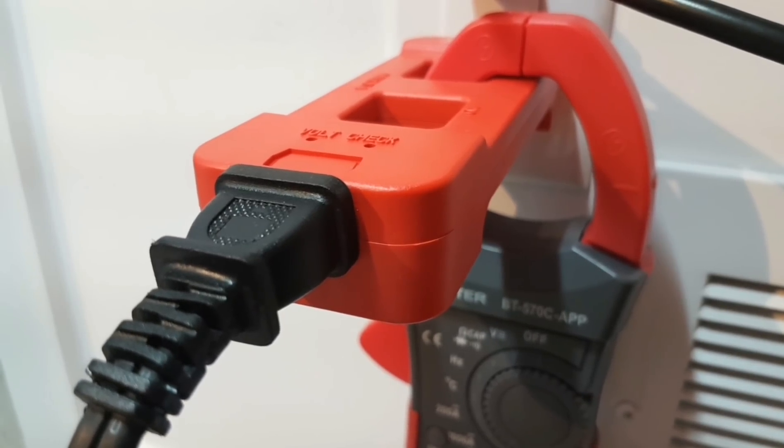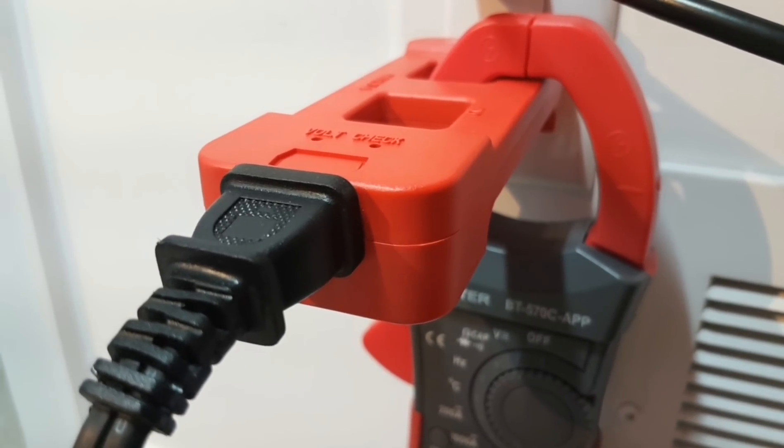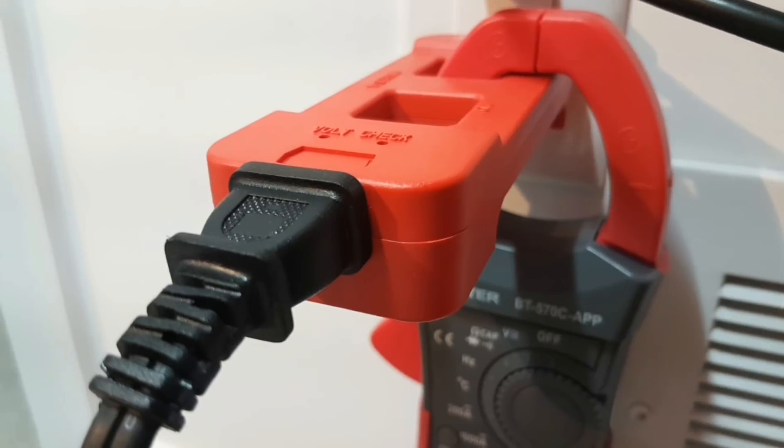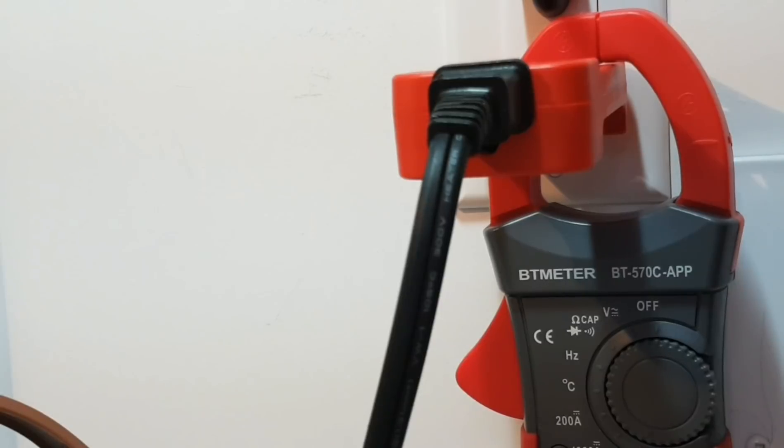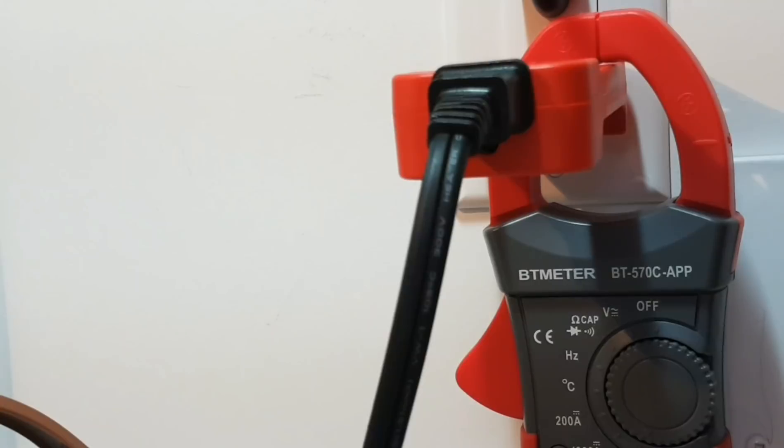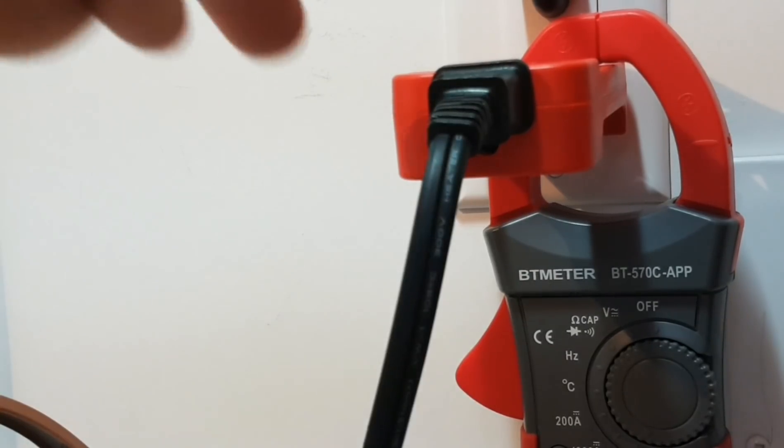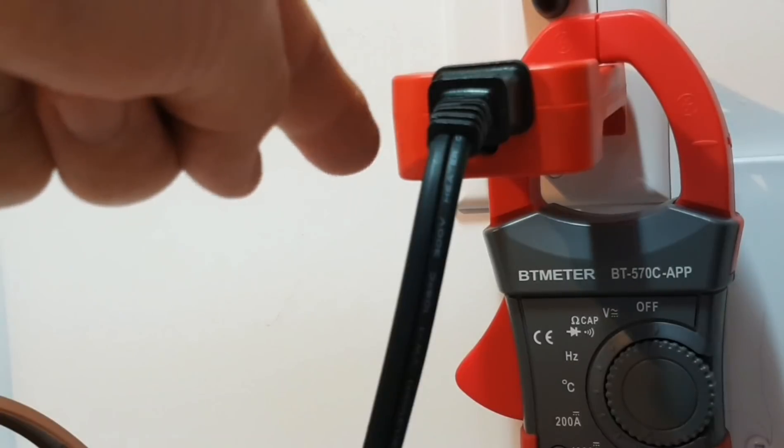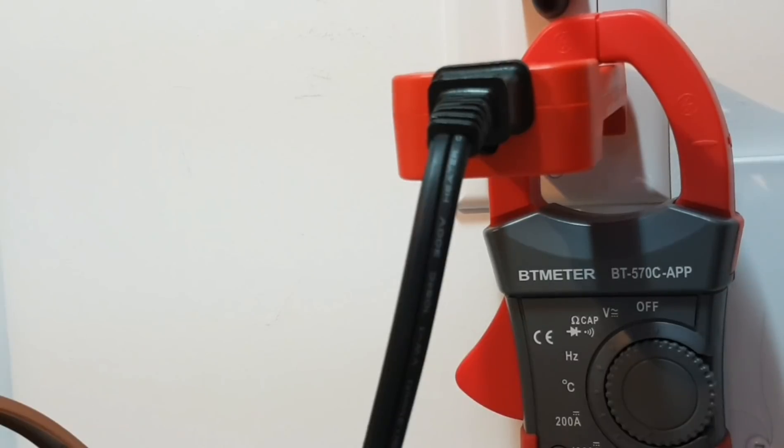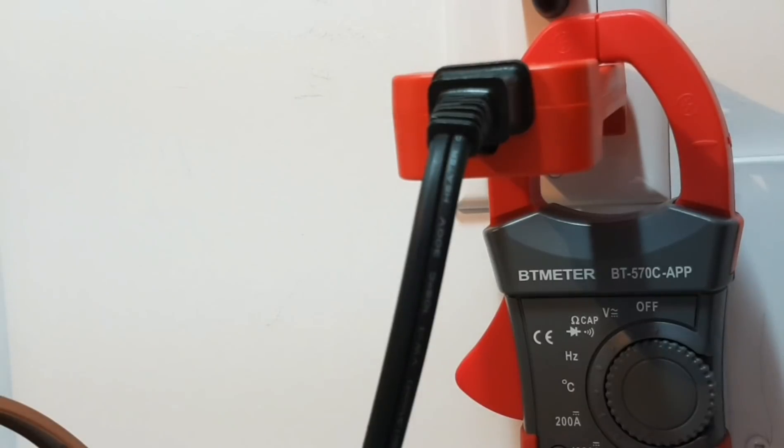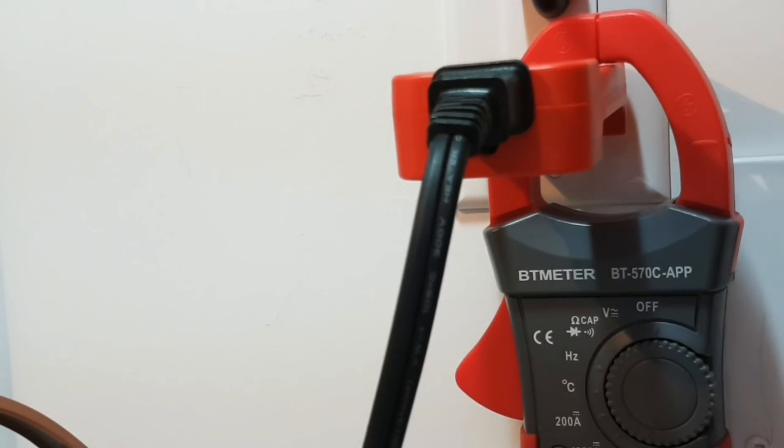What we're going to do now is utilize the line splitter to get a current draw from this space heater. What this is going to do is it separates the hot from the neutral and ground wires. So on a standard 120 volt outlet, current measurements can be made with the current clamp. If we didn't utilize this line splitter, what's going to happen is the clamp is going to measure the load current in both directions, effectively canceling out any test measurement.